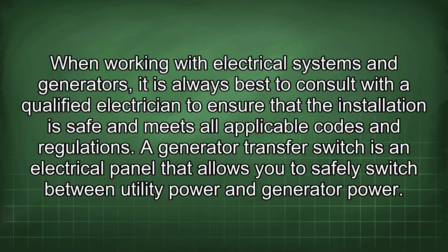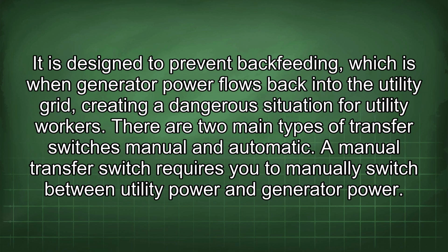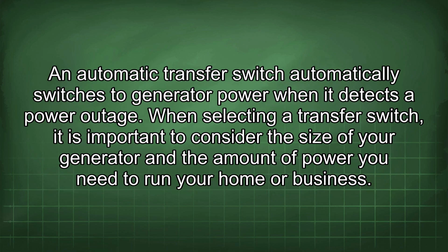A generator transfer switch is an electrical panel that allows you to safely switch between utility power and generator power. It is designed to prevent backfeeding, which is when generator power flows back into the utility grid, creating a dangerous situation for utility workers. There are two main types of transfer switches, manual and automatic. A manual transfer switch requires you to manually switch between utility power and generator power. An automatic transfer switch automatically switches to generator power when it detects a power outage.